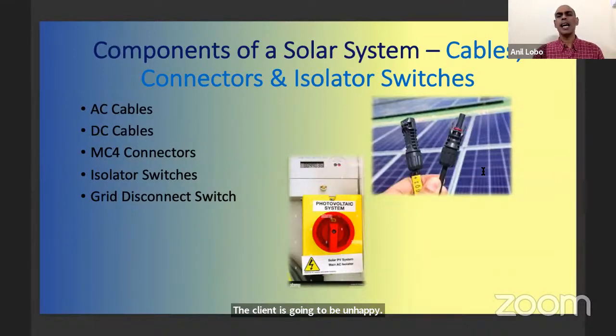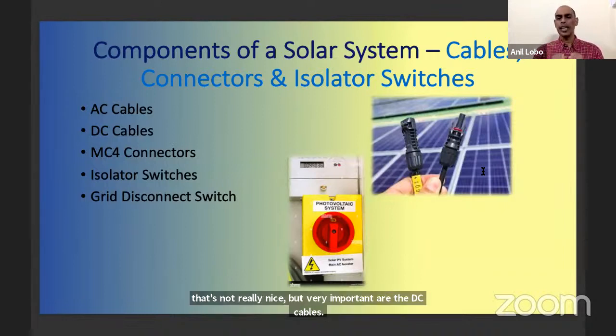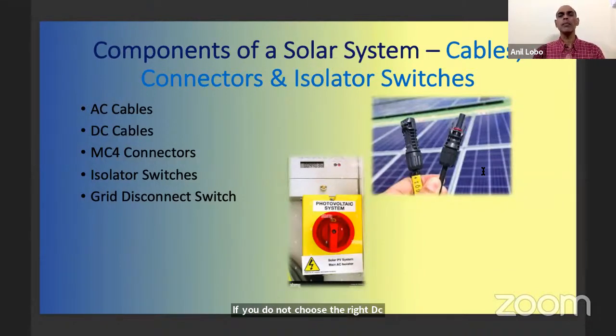But very important are the DC cables. If you do not choose the right DC cables, your system will overheat. And we know that with DC current there's a higher resistance, so they tend to overheat. You have to not only choose good quality DC cables, preferably copper cables, but you also have to choose the right size.